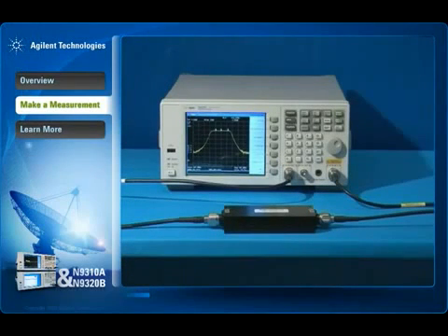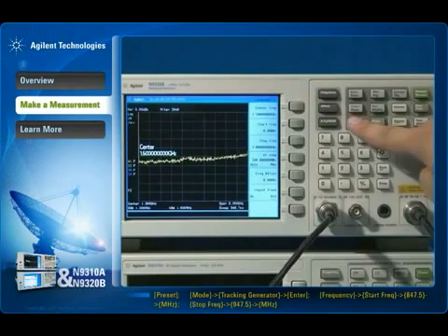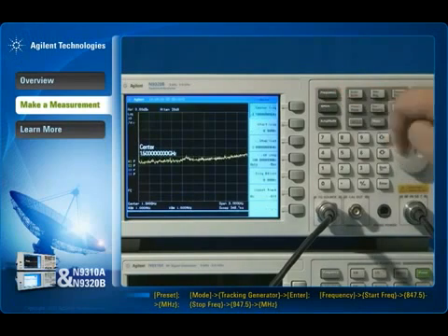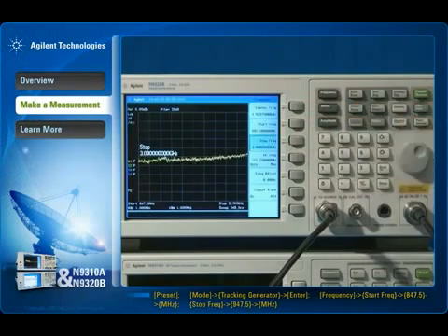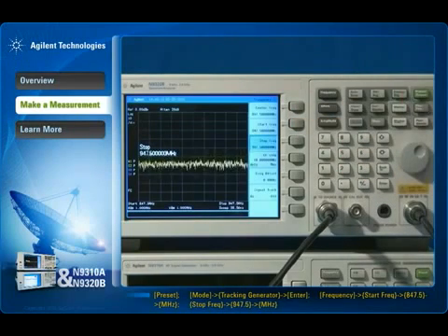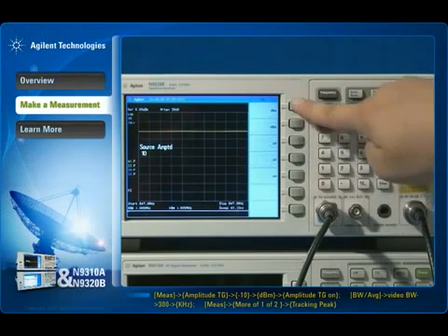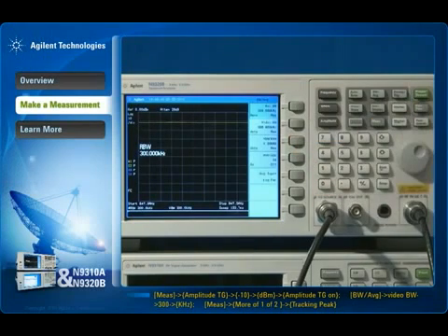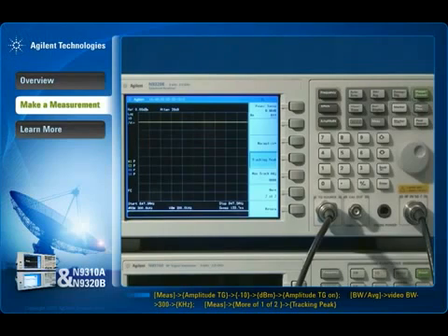The optional tracking generator adds a new dimension of power to the N9320B spectrum analyzer. This demonstration shows how the tracking generator lets you measure the insertion loss of a filter. Turn on the tracking generator mode and set the start and stop frequencies. Set the output power to minus 10 dBm. Reduce the resolution bandwidth to increase measurement sensitivity and smooth the noise. Activate the tracking peak to correct the frequency offset between the output frequency of the tracking generator and the input frequency of the analyzer.